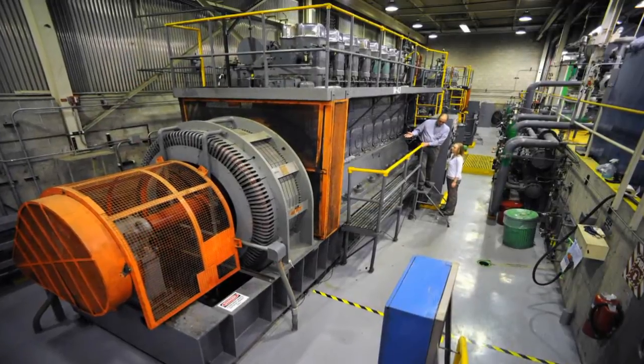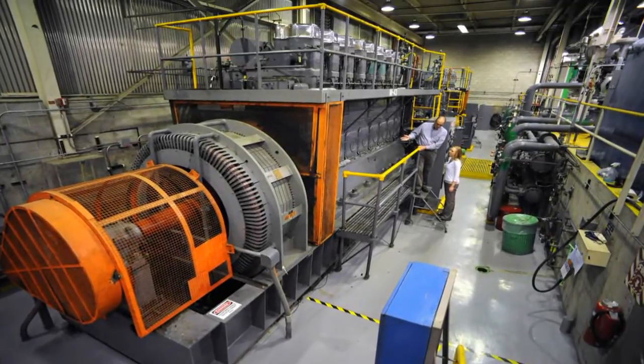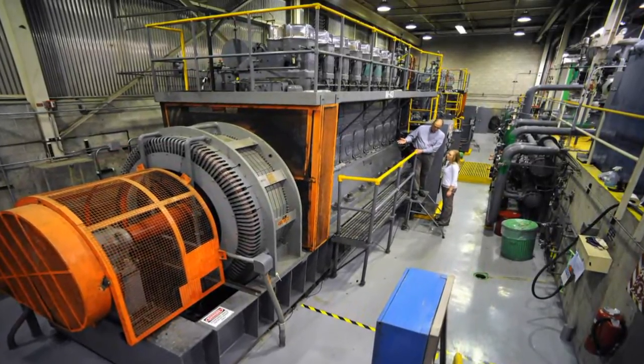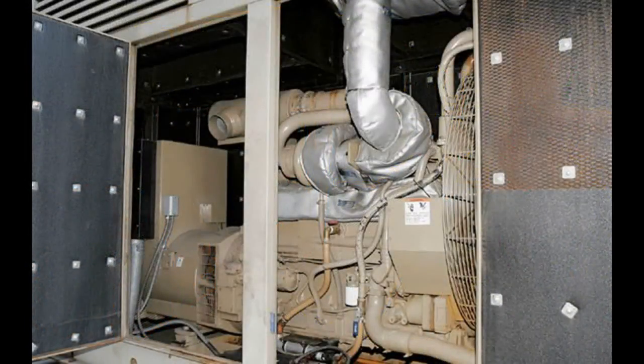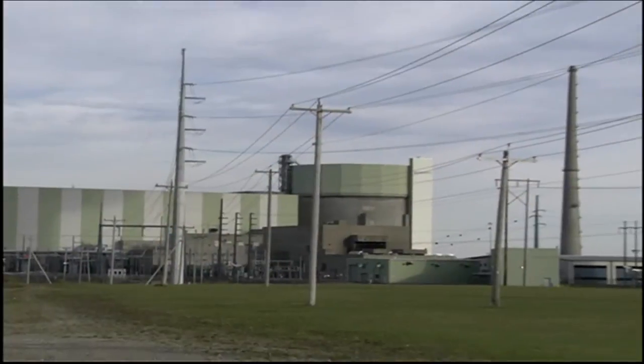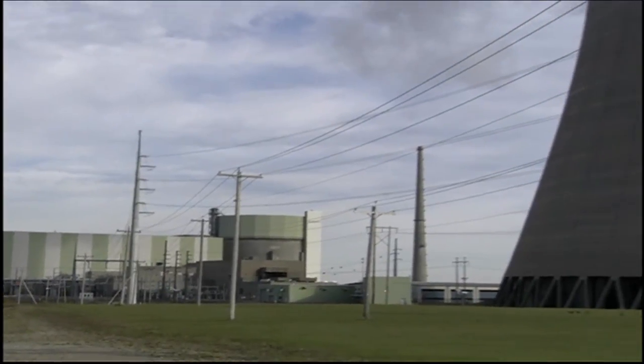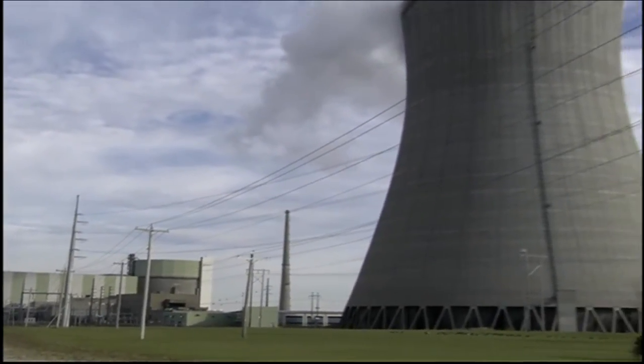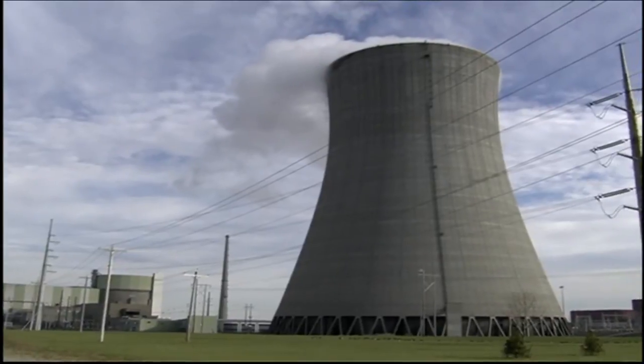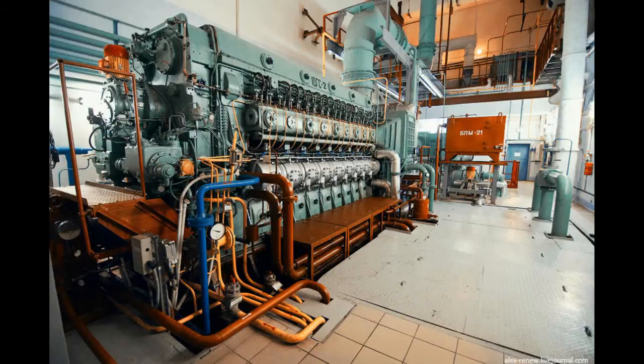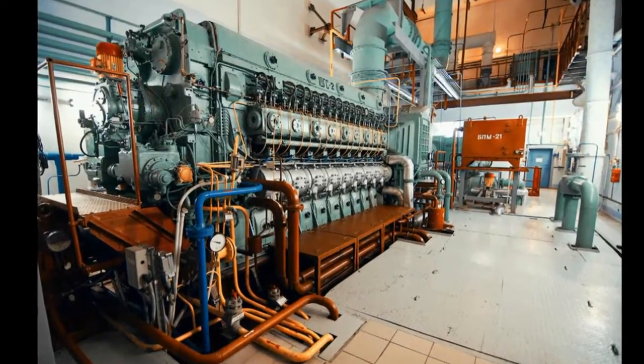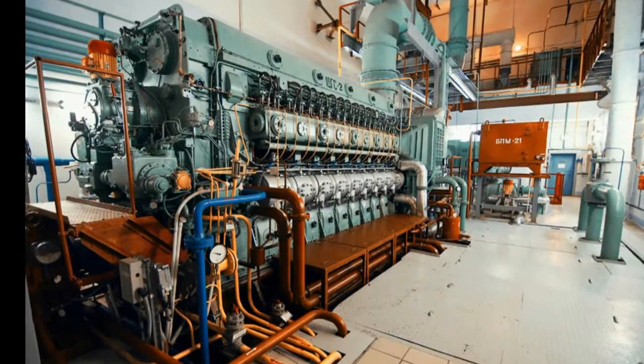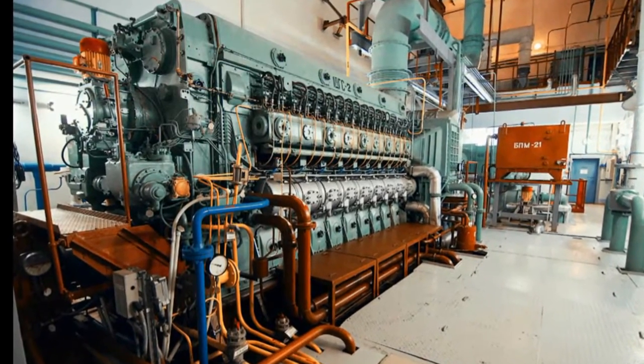The second demonstration centers on diagnosing problems in a diesel engine within an emergency diesel generator system. It is essential that these engines start and run reliably because the emergency diesel generator provides power to operate the plant when the external power grid is not available. Proper engine valve timing is essential for the engine to start and meet its load requirements. Cylinder temperatures in the engine can be used to diagnose problems with the valve timing and other common faults.